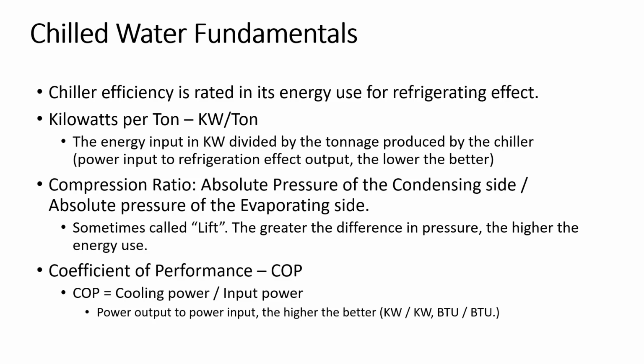That's the fundamental basic, that's where it came from over 100 years ago. That works. Very good. Thank you. Yeah, that's where we get the term. And we still rate the equipment and how much heat it moves. And in this case, it's going to be 12,000 BTUs per ton per hour. That's 1 ton, or 12,000 BTUs is 1 ton of refrigeration in an hour.